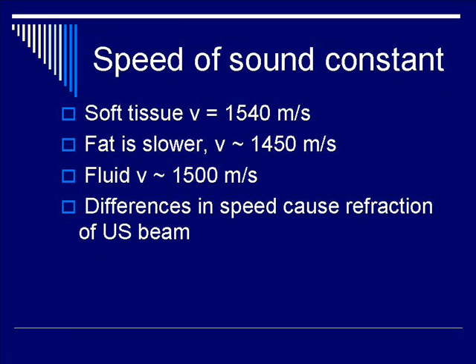The next assumption is that the speed of sound is constant. That is very far from the truth. In soft tissue, the velocity of sound is 1540 meters per second. However, in fat it is slightly slower at 1450 meters per second, and in fluid — which appears anechoic in ultrasound — the velocity is about 1500 meters per second. These differences in speed across different media will cause refraction of the ultrasound beam, which, by virtue of the bending of the beam, causes images to be located in places you did not expect.